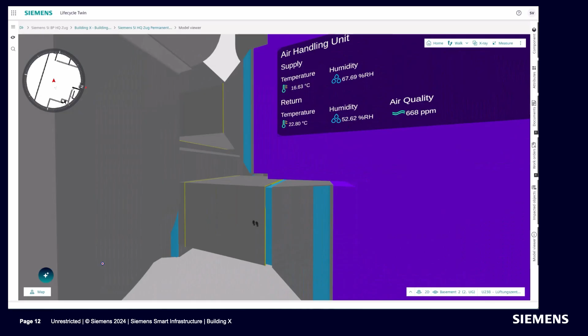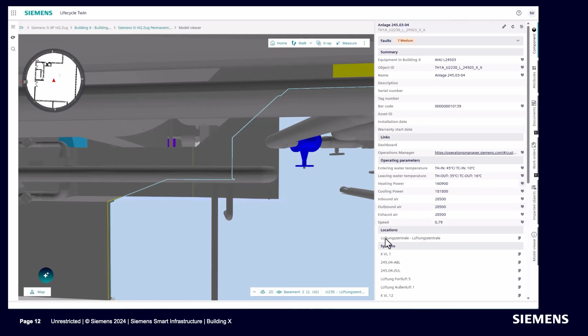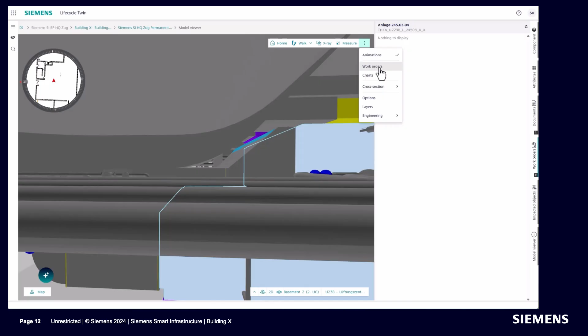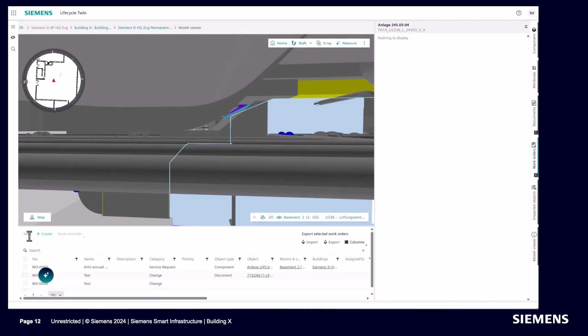I also pull up information related to that AHU, look at the faults related to it, and check the different operating parameters and the different work orders that are there on this particular AHU. And it looks like, yes, there is also something open that needs to be serviced immediately because there is a problem with the discharge air temperature.